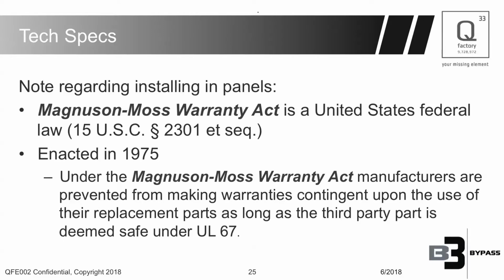A quick note on warranty. Some panel manufacturers make claims stating that you cannot put third-party breakers inside their panel. Well, Congress in 1975 passed an act known as the Consumer Protection Act. The official name is the Magnuson-Moss Warranty Act. Basically, under that act, a manufacturer cannot make their warranty contingent upon using manufacturer's only parts. This would be similar to a car. If you replace a part in the car using a non-Ford part and you have a Ford car, they can't void the warranty. Some panel manufacturers are saying to installers you can't use the B3 because it's not made by them. Actually, that's not true. So I just wanted to highlight that.